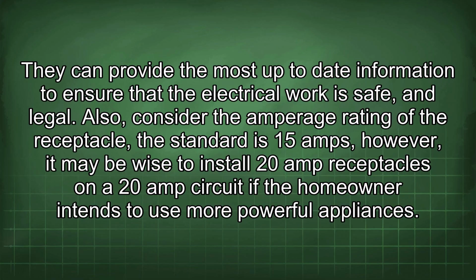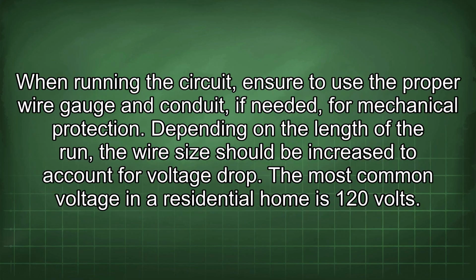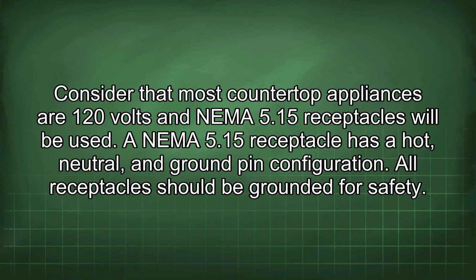use more powerful appliances. When running the circuit, ensure to use the proper wire gauge and conduit, if needed, for mechanical protection. Depending on the length of the run, the wire size should be increased to account for voltage drop. The most common voltage in a residential home is 120 volts. Consider that most countertop appliances are 120 volts and NEMA 5-15 receptacles will be used. A NEMA 5-15 receptacle has a hot, neutral, and ground pin configuration. All receptacles should be grounded for safety.